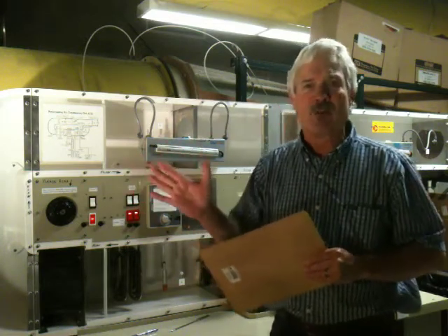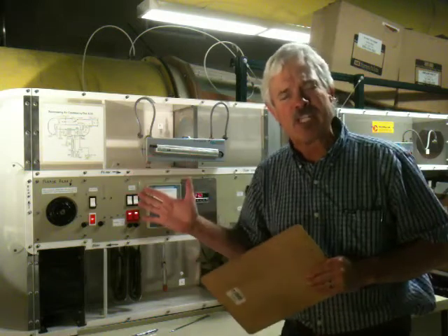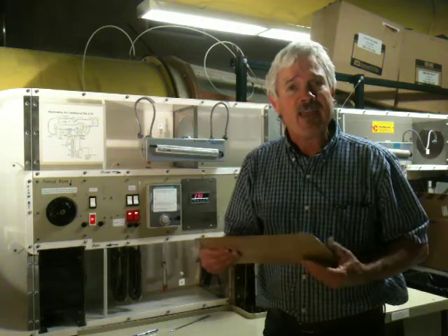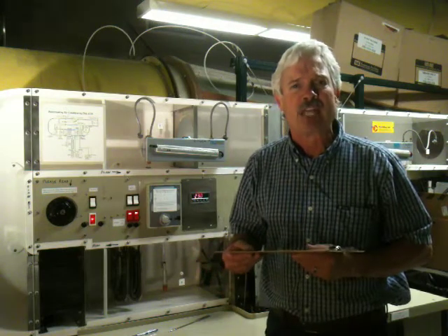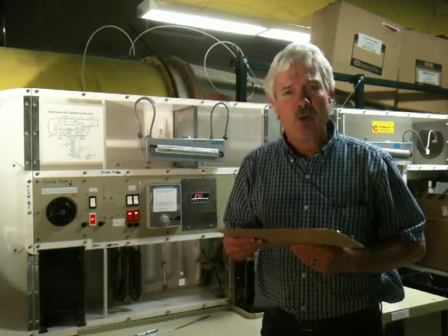For station D, that is downstream from the refrigeration unit, but it's also fairly close to the reheater. And even though it's upstream from the reheater in terms of the airflow, it's still exposed to the radiant heat from the reheater. So the temperatures at D went up by a little bit. And then, as we would expect, the temperatures at station E, which is downstream from the reheater, went up by quite a bit. So there is that data there.